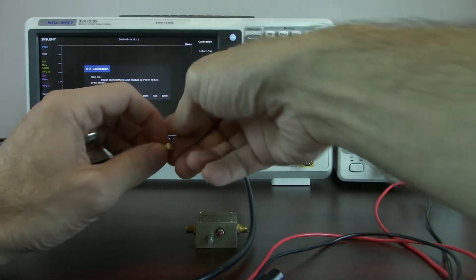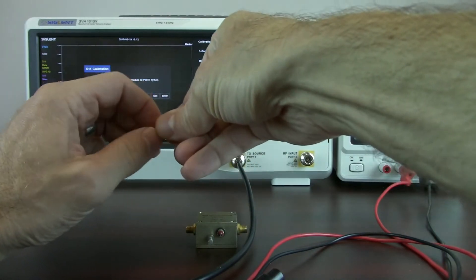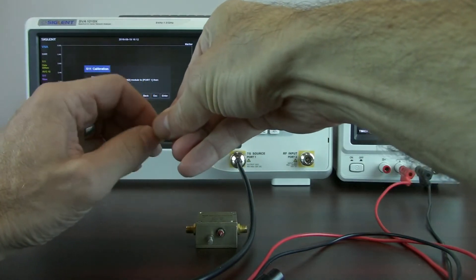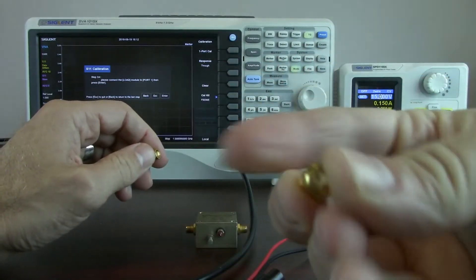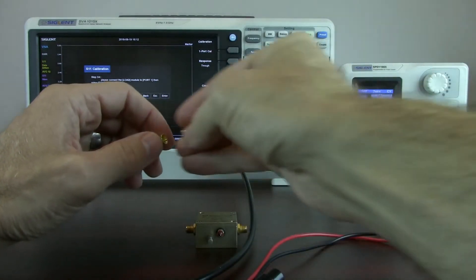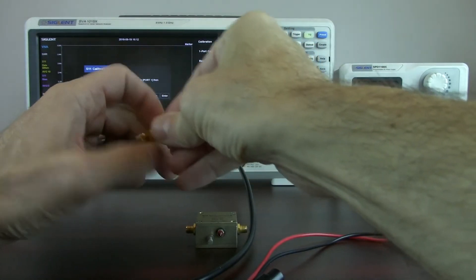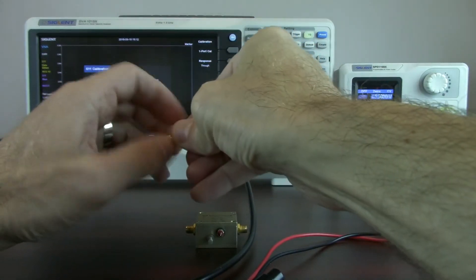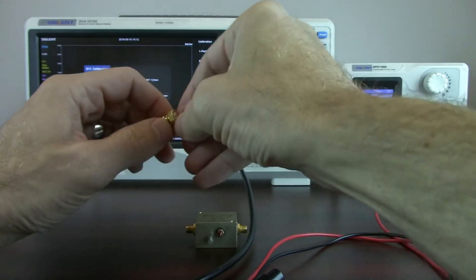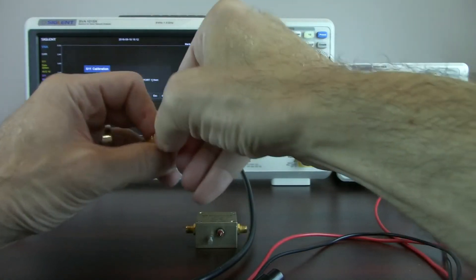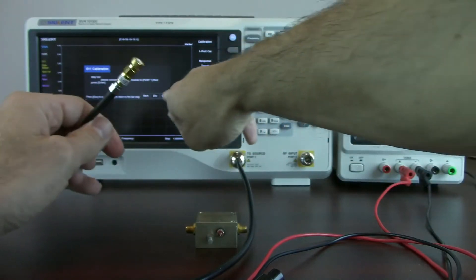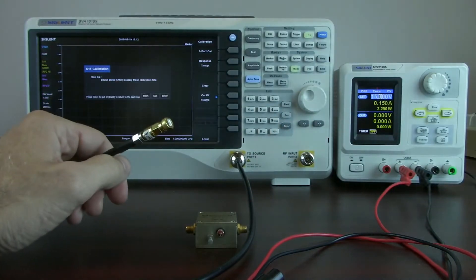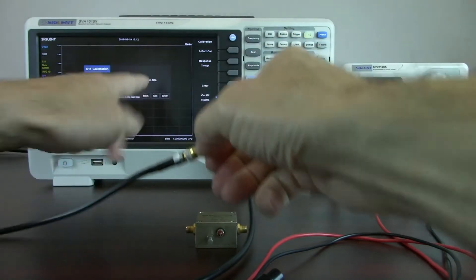And now we want to connect the load module. So we're going to disconnect that short. And now we've got a load, this is a 50 ohm load, and we're going to connect it and hit enter. Now we're calibrated. So now we've applied that calibration.